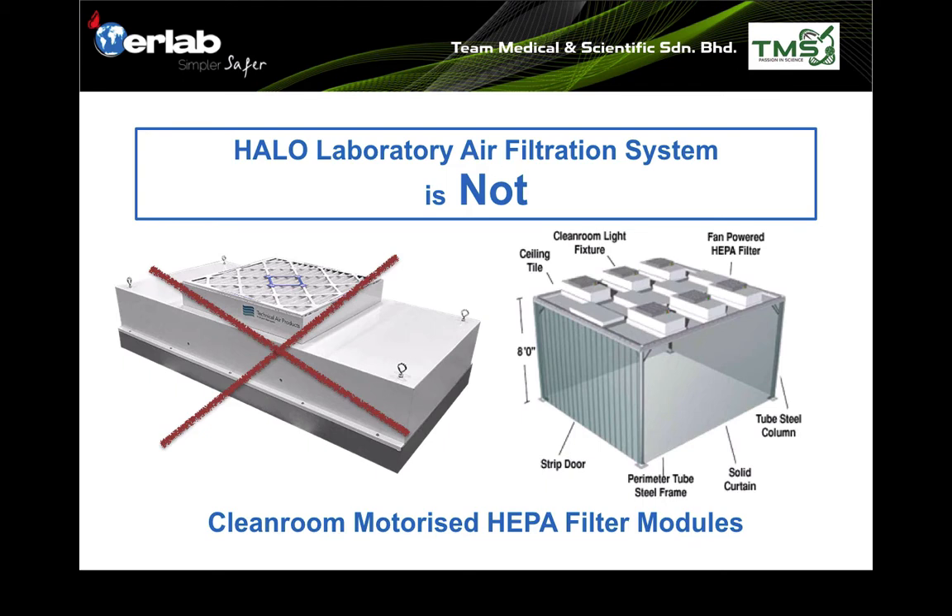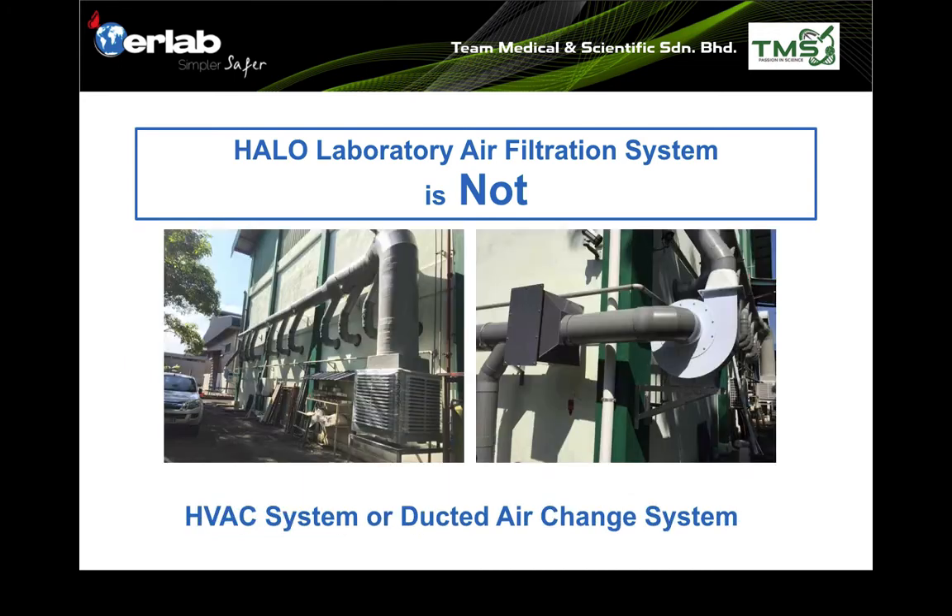HEPA filter modules produce clean air and are used in ISO Class 5 cleanrooms. Whereas the HALO laboratory air filtration system does not generate positive airflow — it sucks air from the room, filters it, and returns it back to the room. HALO is also not an HVAC system or a ducted air change system, which are used to improve air change in factories.